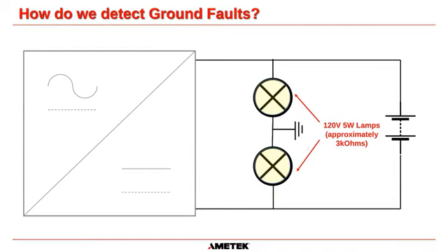So I know through this presentation, there have been so many people shouting at the screen that when I measure positive to ground or negative to ground on my system, it doesn't show me 135 volts and 0 volts. It shows me 65 volts and 65 volts. And you are correct, because somebody has added ground fault detection to either your DC bus or your charger. To monitor ground faults, you have to give the alarm circuit a reference to ground. And in doing that, basically it splits the bus in half.